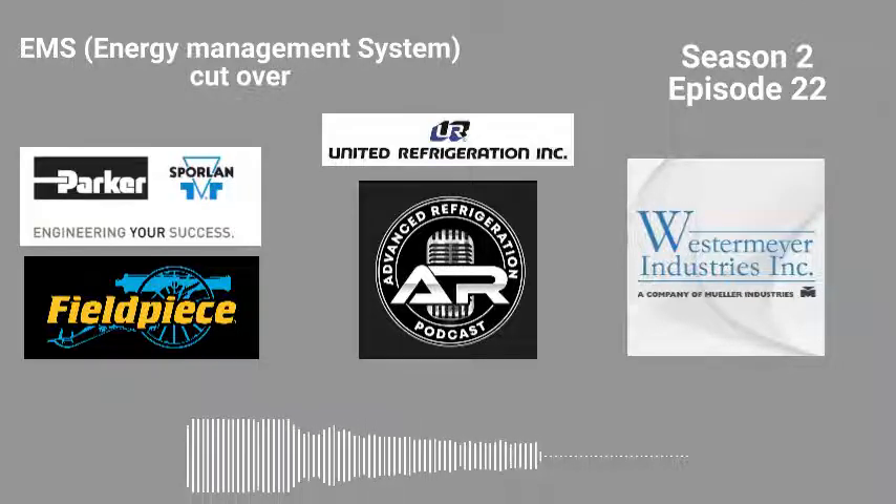After we recorded that podcast, I was talking to another customer who had the same issue. We had a conference call about it — could do tandem compressors, digital control, or hot gas bypass. We went down to meet with them. They were talking about Hussmann — they actually have a kit for sizing the hot gas bypass valve desuperheating. I asked for the part number. Get that kit so you can send it back to the OEM. This needed to be put in. There's a kit for a reason — that's called an engineering boo-boo.